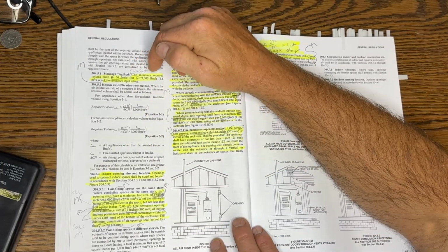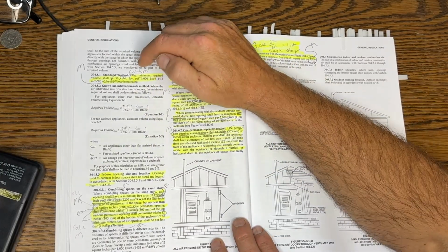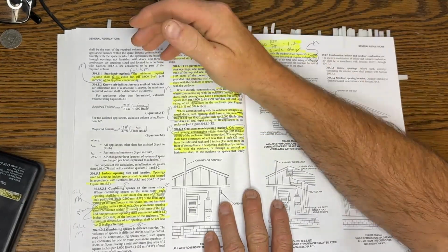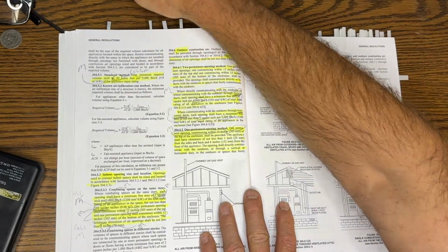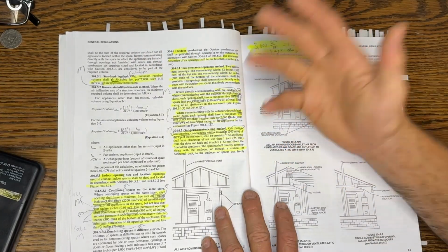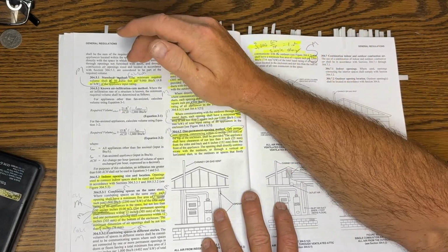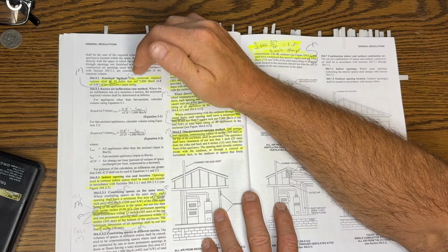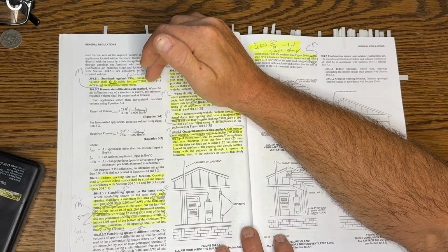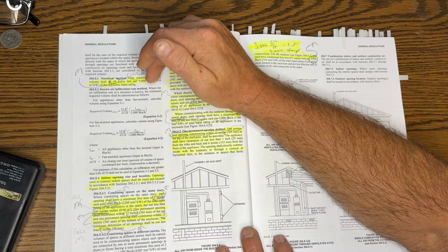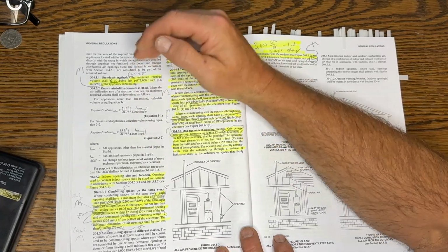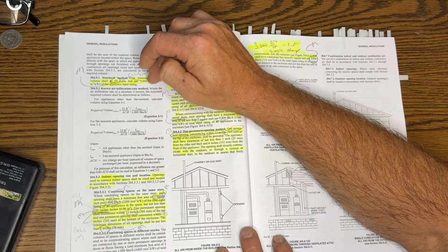Okay, standard method. So when you're calculating like air in a building, so you don't have like a vent, and you're sizing it. Let's say you have like a basement or something like that, a finished basement. You're putting a mechanical room in. This is where this comes into play. So let's say you had 100,000 BTU furnace or 200,000 or something like that. You have to have 50 cubic feet volume of air per 1,000 BTU.